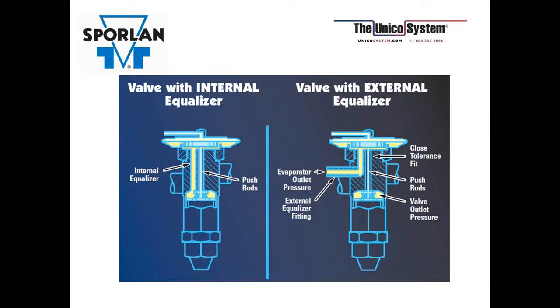Our distributors are designed to give an additional pressure drop through the nozzle orifice to create a higher velocity of the vapor-liquid mixture so that you get a nice homogeneous mix as it hits the dispersion cone and equally feeds the feeder tubes. So in the example, if you were using an internal equalized valve, then it wouldn't pick up that additional pressure drop. For R22, that nominal pressure drop would be about 35 pounds, and for R410A, it would be about 45 pounds through the nozzle and the feeder tubes.